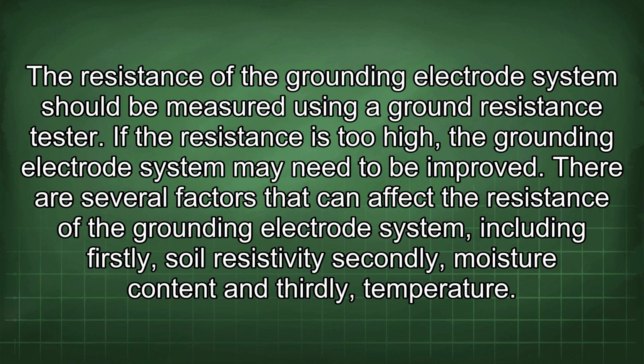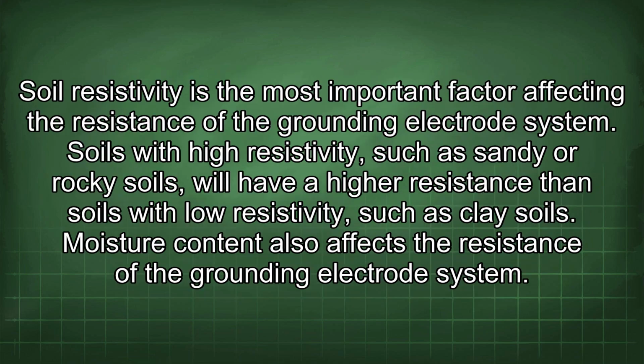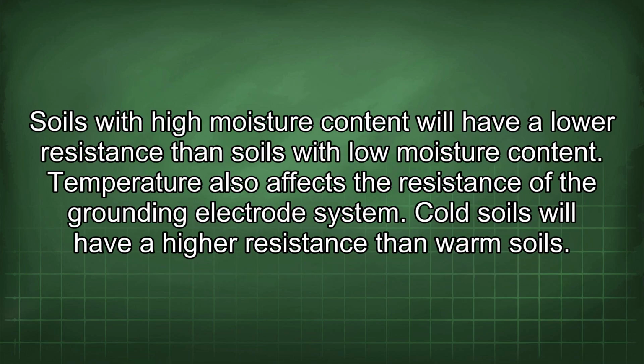There are several factors that can affect the resistance of the grounding electrode system, including firstly, soil resistivity, secondly, moisture content, and thirdly, temperature. Soil resistivity is the most important factor affecting the resistance of the grounding electrode system. Soils with high resistivity, such as sandy or rocky soils, will have a higher resistance than soils with low resistivity, such as clay soils. Moisture content also affects the resistance of the grounding electrode system. Soils with high moisture content will have a lower resistance than soils with low moisture content.